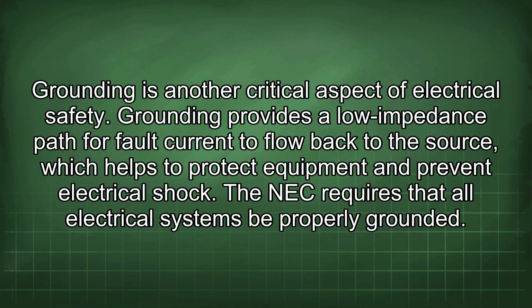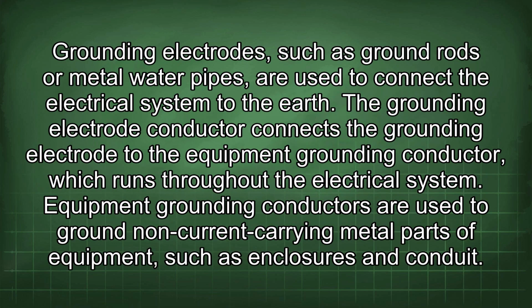Grounding is another critical aspect of electrical safety. Grounding provides a low impedance path for fault current to flow back to the source, which helps to protect equipment and prevent electrical shock. The NEC requires that all electrical systems be properly grounded. Grounding electrodes, such as ground rods or metal water pipes, are used to connect the electrical system to the earth.